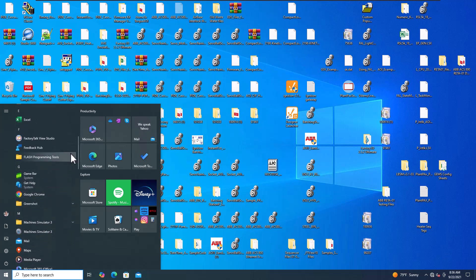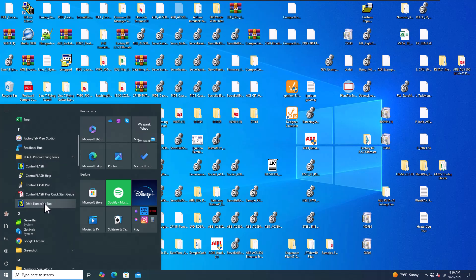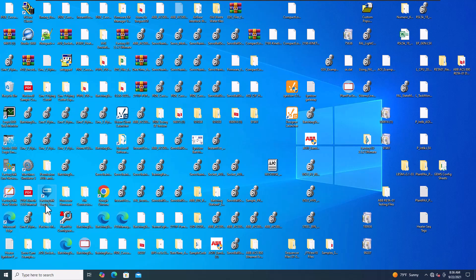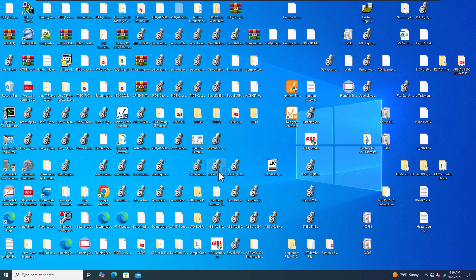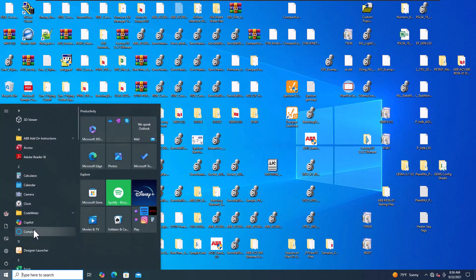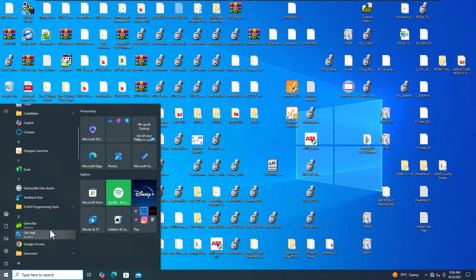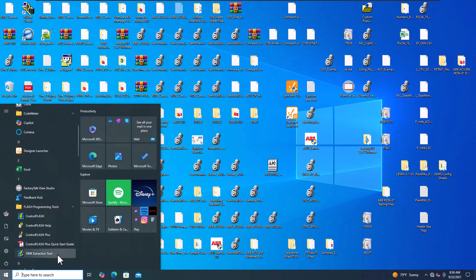It will be a DMK file, generally speaking. And you just come over here to your ControlFlash, right here, and you want to go to DMK Extractor. As soon as you do that, if you download the DMK, which is going to be your firmware, you do the DMK Extractor, it automatically adds it to your ControlFlash. The DMK Extractor does take a minute, so be very patient. It's called the DMK Extraction Tool. It does take a minute to start up, so I want you to make sure that you know that. Even though you've clicked it once, don't click it multiple times, because then you're going to get into that whole little thing where Windows opens up multiple instances.